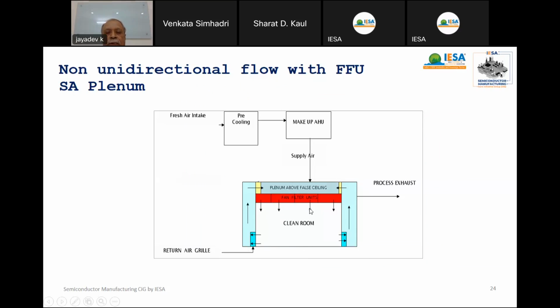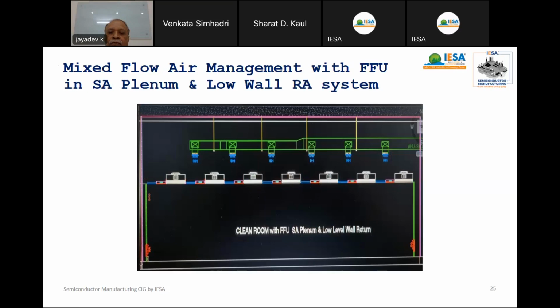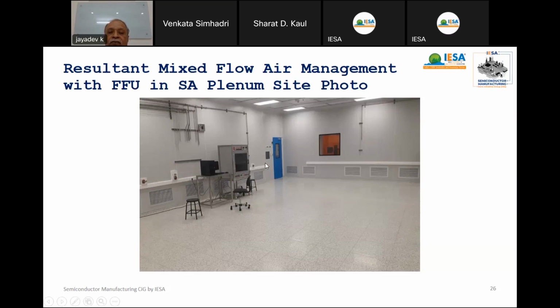Another method of achieving an ISO 6 clean room: how it looks. Here we supply the required air for controlling temperature and humidity between the false ceiling and the ceiling. The ceiling is also encapsulated using some puff material. So air is sucked from this, goes to the return riser, and recirculates. This is another method of constructing the clean room. This is the result of ISO 6 using mixed flow.